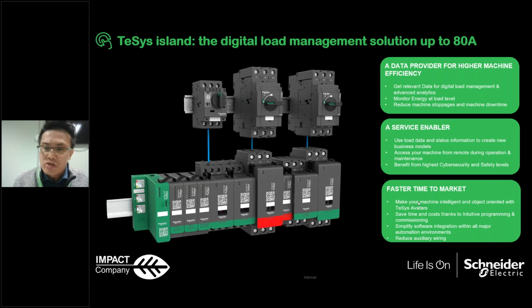It is also actually faster to market with the TeSys Island because it makes your machine intelligent and object oriented with the avatar. You can imagine the avatar as something like a function block, and you can clone the function block very easily because it's all well predefined inside the product. You save time and cost for the commissioning because for basic pump applications, you don't need a PLC to program it. You just need to configure it on the TeSys Island, and you can achieve autonomous control. We will talk about that more later.